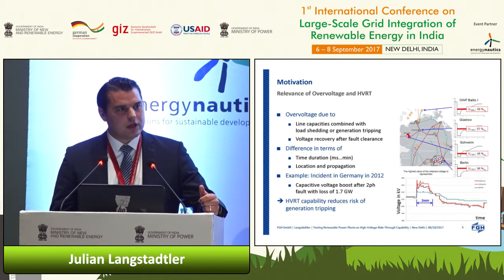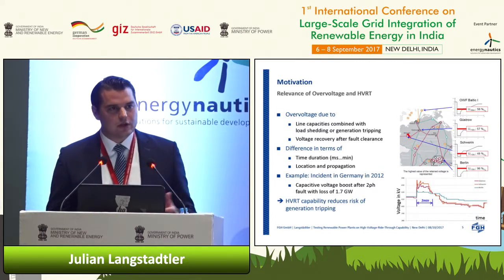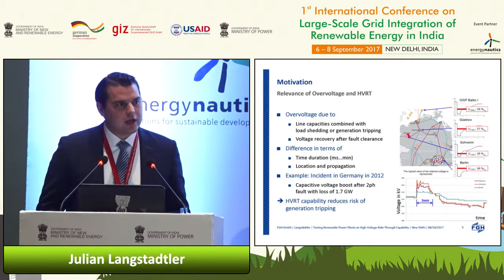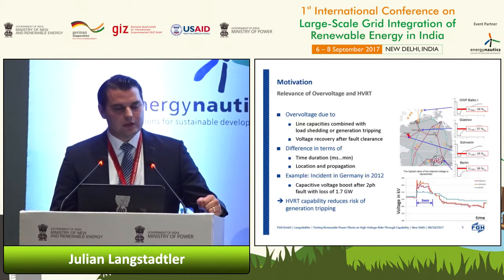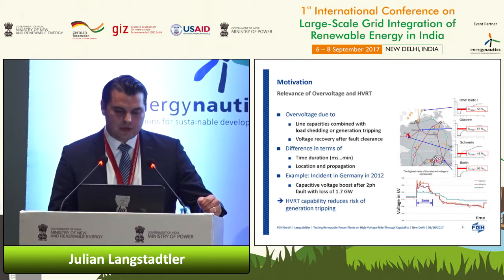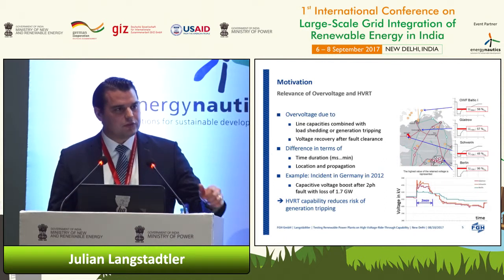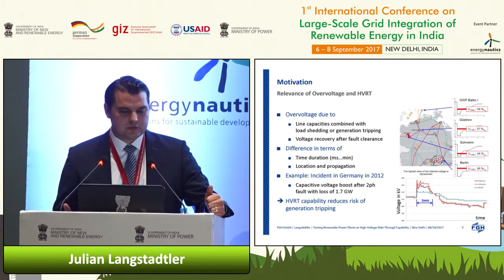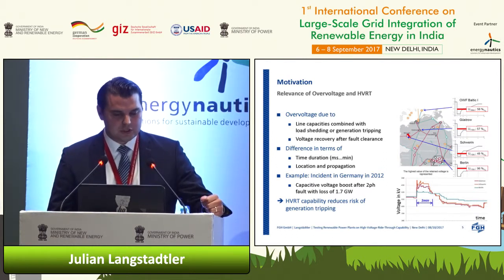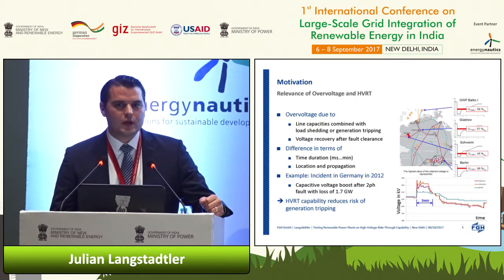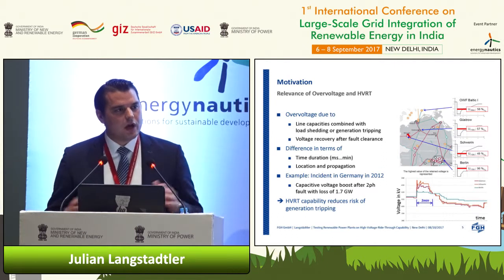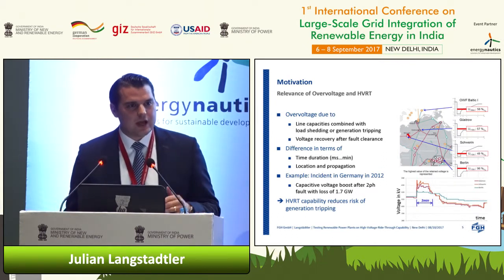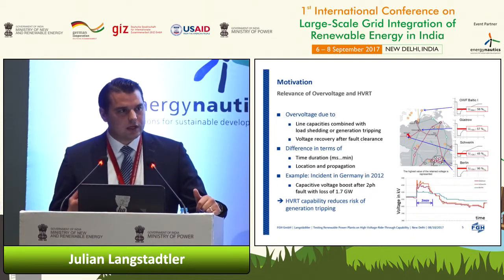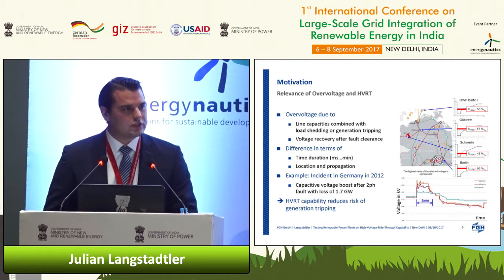So overvoltage may occur in the system due to, on the one hand, maybe line capacities for long transmission lines that are combined with load shedding or also generator tripping. Or on the other hand, after a fault recovery, when a system failure occurred and the fault was cleared, directly after fault clearance, when you have a very short peak in the voltage after recovery. However, these two phenomena, they differ in terms of time duration. So we on the one hand talk about milliseconds, whereas for the load shedding and the unloaded transmission lines, we talk about minutes. And they also differ in terms of location and system propagation. So that means one are only regional phenomena that do not have a wide impact on the system itself. However, load shedding and also generator tripping may affect a huge range of the system.